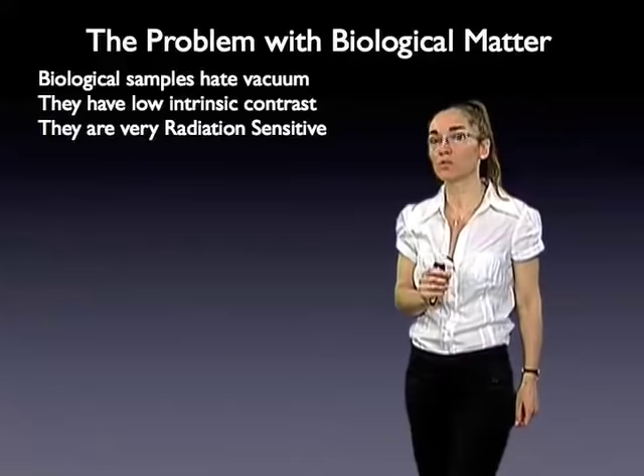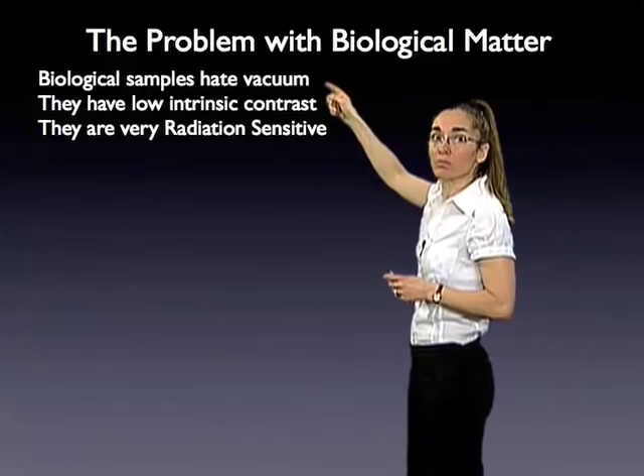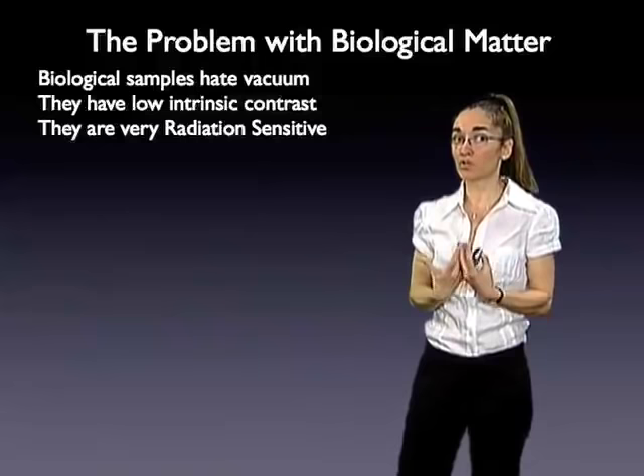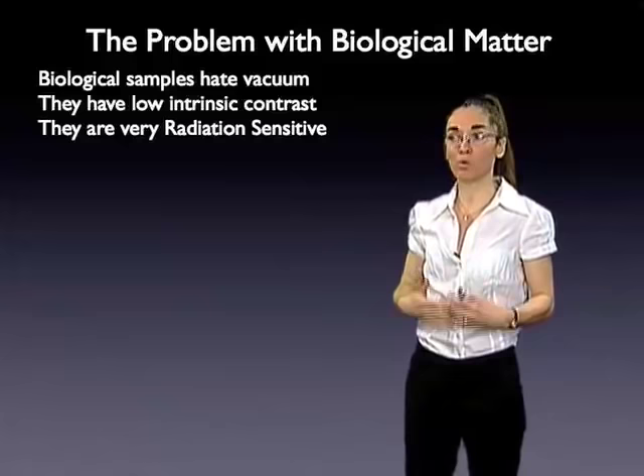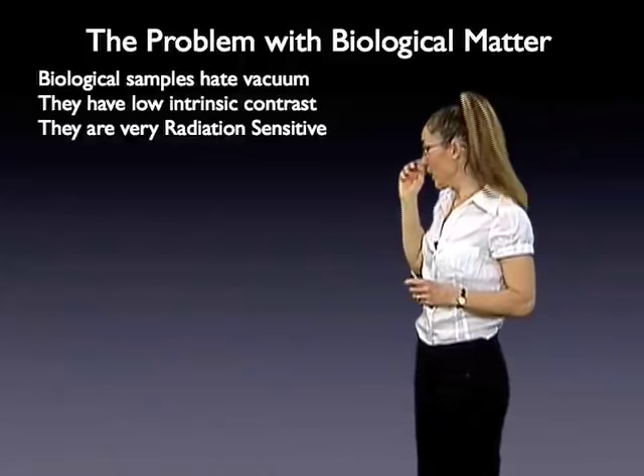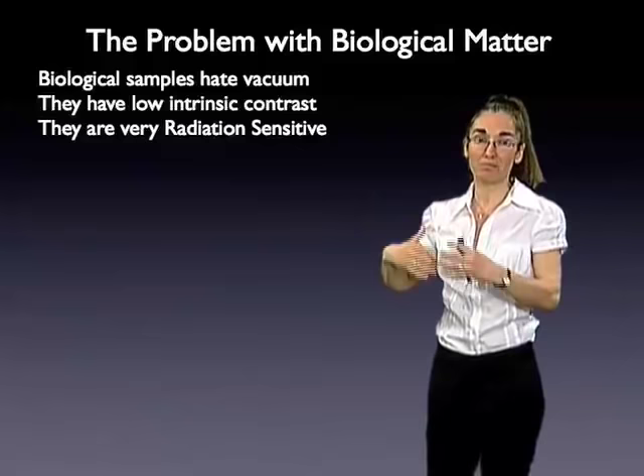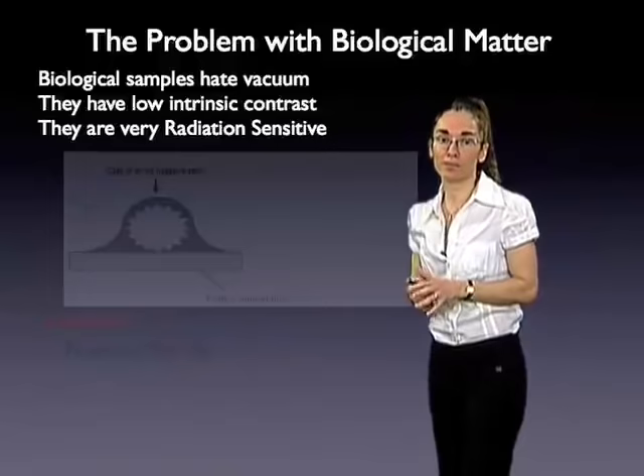Let me review what the problems are that are unique to biological organic samples. First of all, all biological material lives in aqueous solution, and by definition they hate the high vacuum in the column of the electron microscope. The other thing is that the atoms biological materials are made of — nitrogen, carbon, oxygen — have basically the same scattering power as the water surrounding them, so they have very low intrinsic contrast. And most importantly, they are very radiation sensitive: when inelastic scattering occurs, the sample gets ionized, generating radicals that move around the sample and break all the bonds, basically making the whole thing explode.